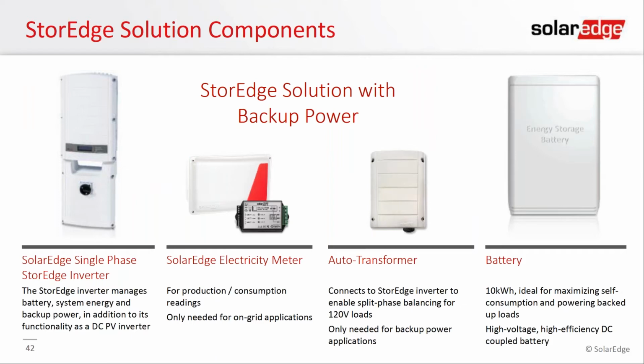We have our StorEdge inverter, which is a 7.6 kilowatt AC inverter, also available as a 3.8 kilowatt AC inverter, with our StorEdge interface connection unit. That's the DC disconnect on the bottom of the inverter, and it has a whole bunch of connection points for the battery and for the SolarEdge electricity meter. This is a consumption meter that measures energy coming and going to and from the home. The auto transformer you only need if you're planning on doing backup power. If you're only doing time of use arbitrage or demand shaving, then you don't need the auto transformer.